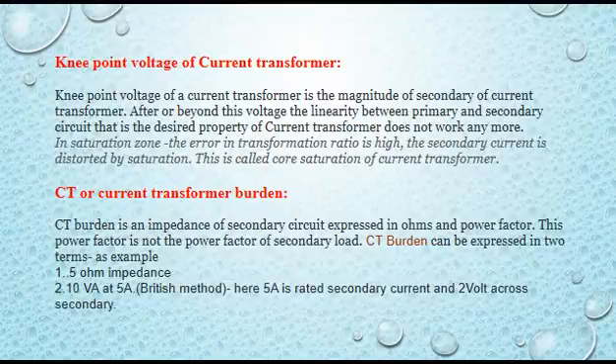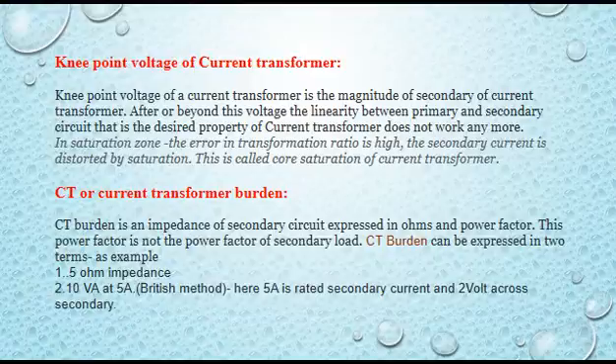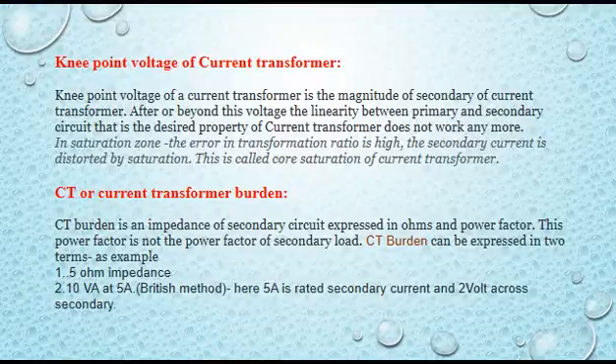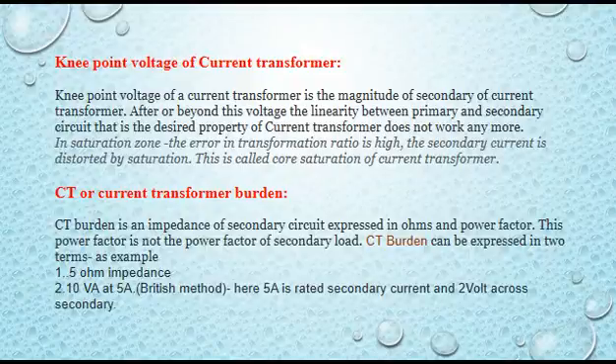CT burden is the impedance of the secondary circuit expressed in ohms and power factor — note this power factor is not the power factor of the secondary load. CT burden can be expressed in two ways: for example, as 5 ohms impedance, or as 10 VA at 5 ampere rated secondary current, which gives 2 volts across the secondary. The second is the British method.